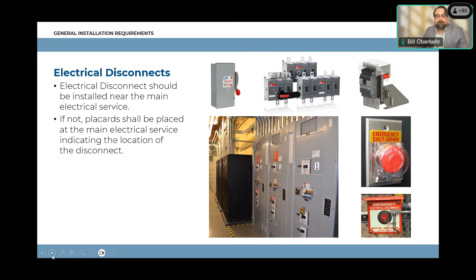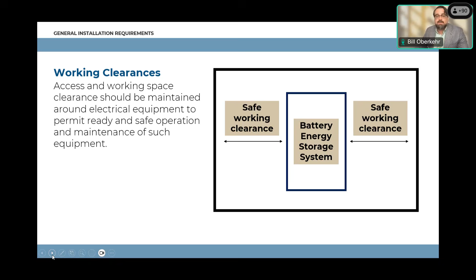So here we have working clearances. So working spaces that may be around the electrical equipment and the energy storage system. The clearance for working on the equipment should be 3 feet. The National Electric Code, NFPA 70, requires this. These clearances should always be unobstructed. Fire departments that may go out to do a site visit should notify owners of the equipment when they are not in compliance with the regulations. So if folks are AHJs or representatives of the local fire department and see less than a 3 foot clearance while the system is under construction, that is something that should be brought to the local jurisdiction and addressed. Next slide, please.